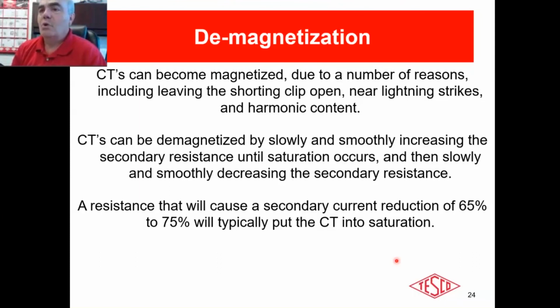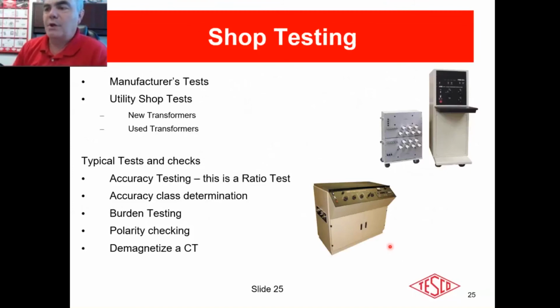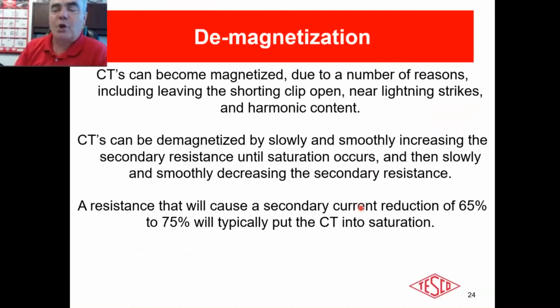Demagnetization. You can magnetize a CT for a variety of reasons, and we'll talk a little bit more about it next week. Demagnetizing a CT can be done very easily. You slowly and smoothly increase the secondary resistance until you saturate the transformer, and then you slowly and smoothly decrease the secondary resistance. When you're working on one of these units, other than some of the older units, a demag is a standard feature. So it's very important when you're testing them in your shop, if you have a piece of equipment, you can do it. You can also purchase equipment that can just do the demagnetization. If you have field equipment, you can do a demag when you do your field testing, okay?